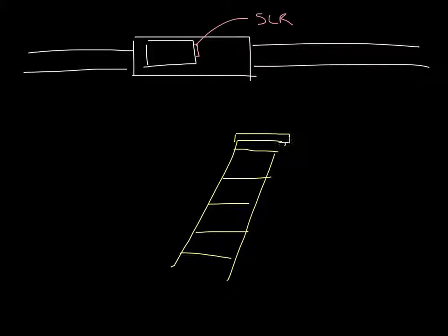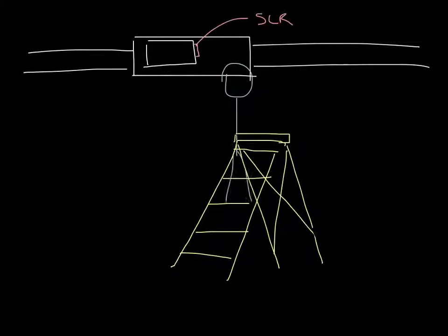As a refresher, a standard PSC motor uses a SCR controller to control the fan speed. The SCR basically cuts the voltage to the motor, which slows it down and reduces your airflow. So let's draw a fan box in the ceiling here, a little ductwork on it and a control box. The SCR is located on the side of the fan box, and to adjust it, you have to get a ladder and a screwdriver. So let's draw a guy on a ladder here, and then put a screwdriver in his hand. Yes, that's a screwdriver. And now that he's up there, he has to turn a potentiometer on the SCR either up or down to increase or decrease the airflow. Some SCRs have little knobs instead of using screwdrivers, but you get the point.